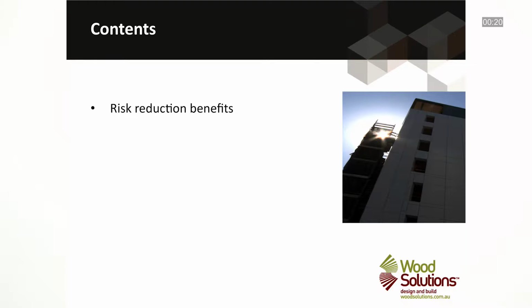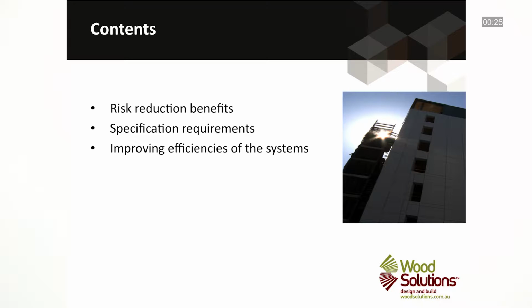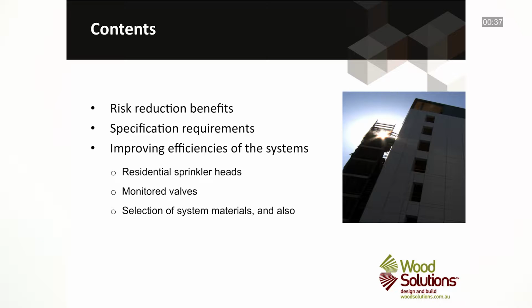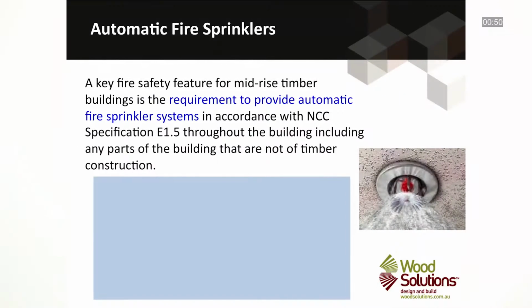In this module, we'll be focusing on the use of automatic sprinkler suppression systems in mid-rise timber buildings. In this presentation, we will cover the risk reduction benefits of sprinkler systems, the specification requirements for different building heights, and we'll also examine a number of different ways to improve efficiencies of the systems, including the use of residential sprinkler heads and monitored valves, the selection of appropriate system materials and processes, and also the importance of protection of voids and concealed spaces. In terms of the fire engineering principles approach for mid-rise timber buildings, arguably the most important requirement is the need to provide automatic fire sprinkler systems.